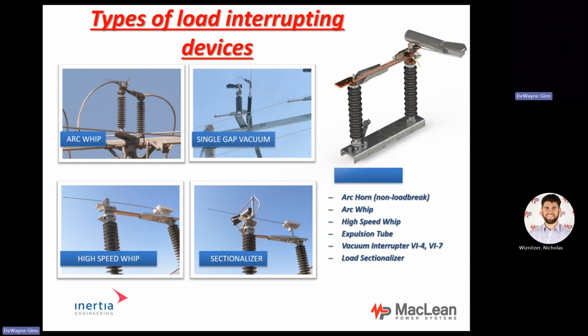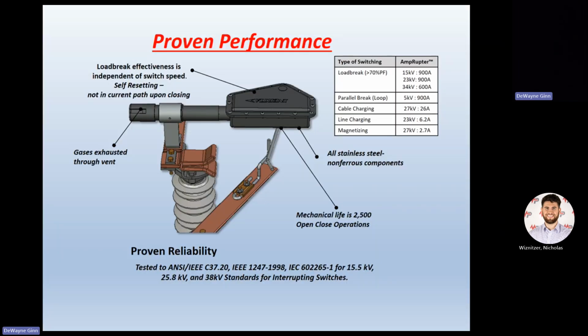Primarily, an arc whip is good for line charge. So when you de-energize a conductor, it still has energy inside of it, and that's called line charge. Consequently, you want to eliminate that line charge, so you can use a whip to do that. As far as interruption, we use an interruption device. This again is an expulsion interrupter. This is good for 600 and 900 amps. Again, the gas extinguishes out of these vents in the back. Inside of here is that white probe. When I make and break with this mechanical side, when it comes out and I activate that control arm, it pulls the probe apart and de-energizes the circuit. On a loadbreak situation, it's good for 600 to 900 amps.